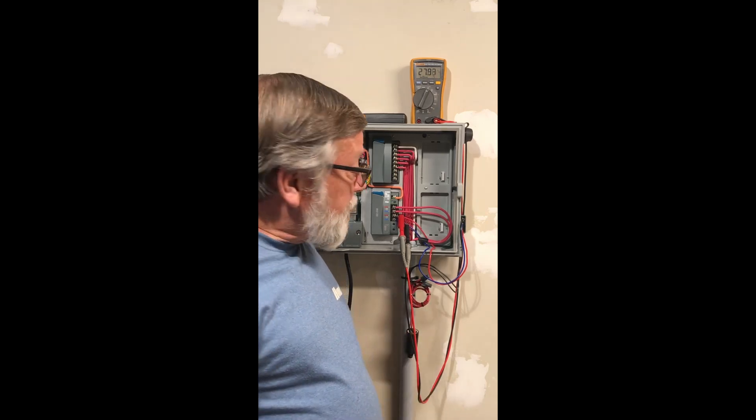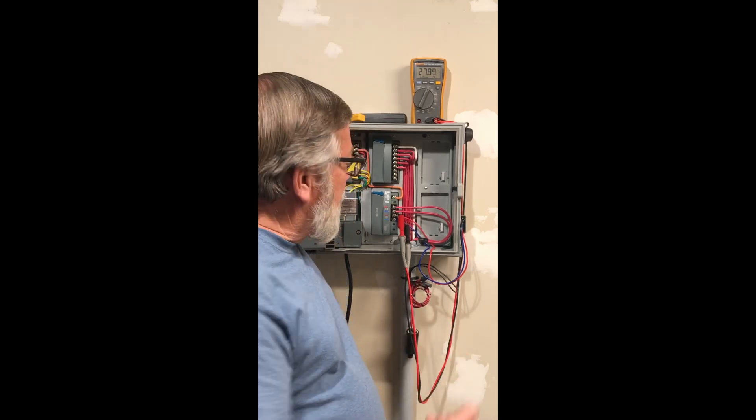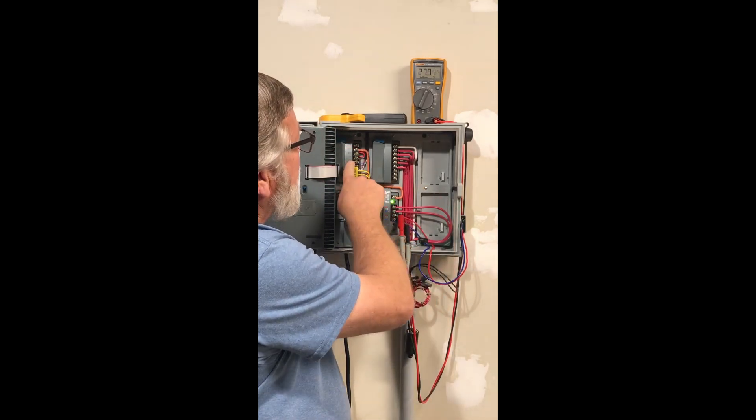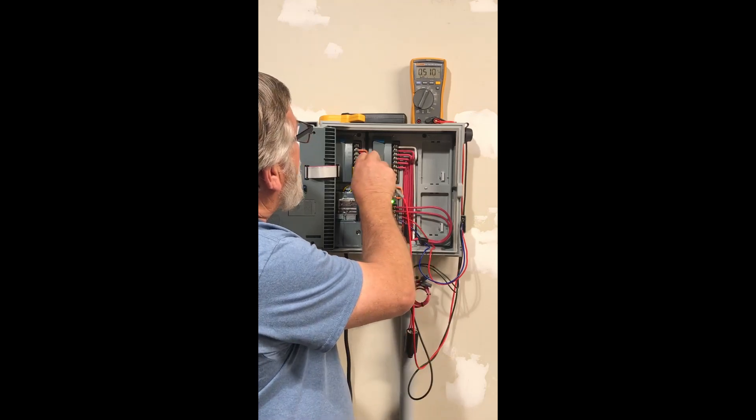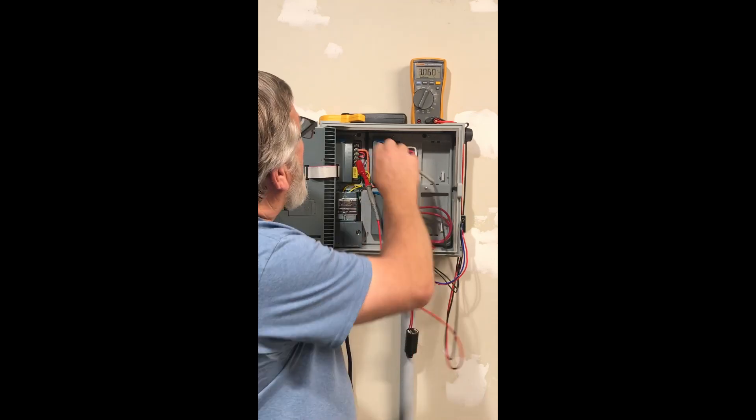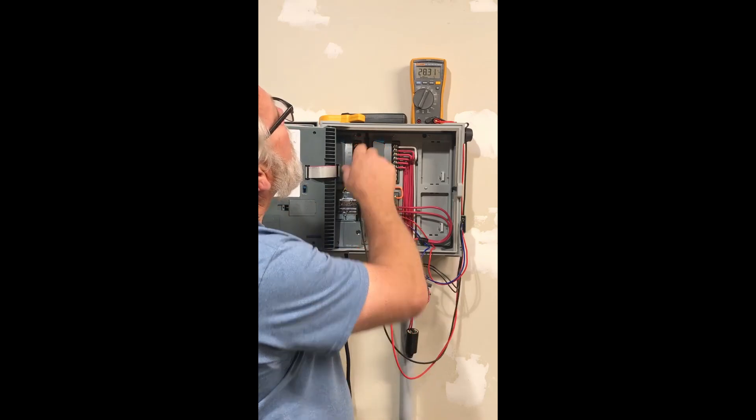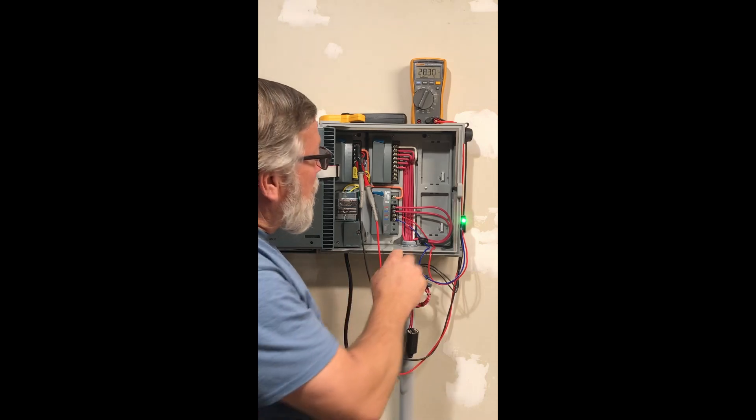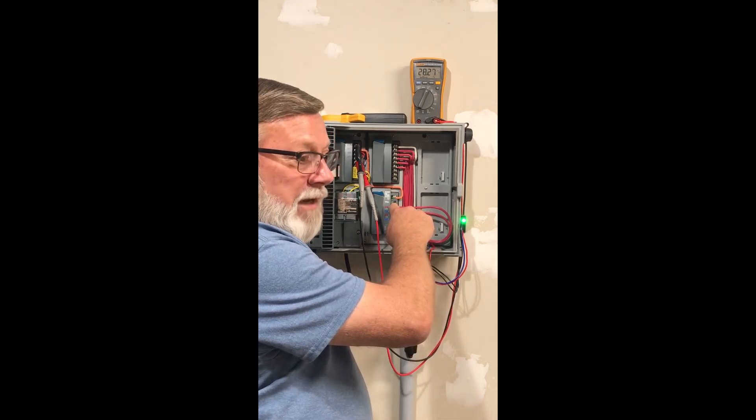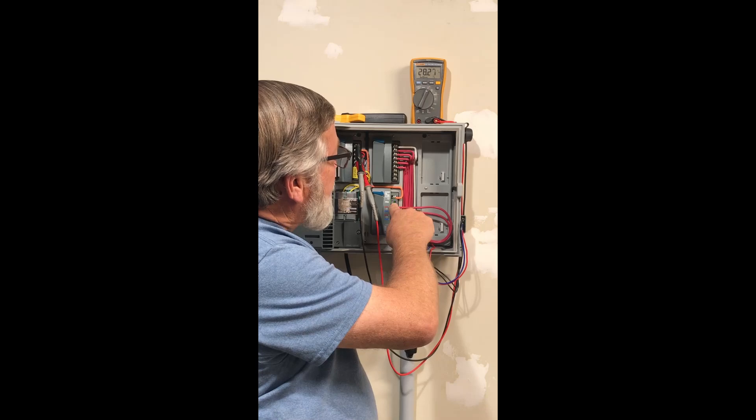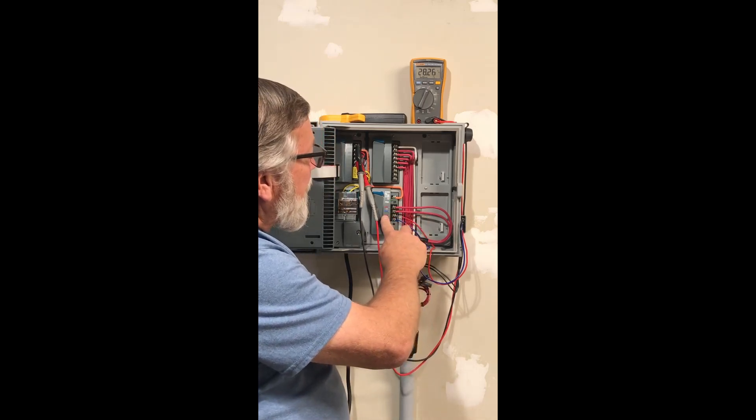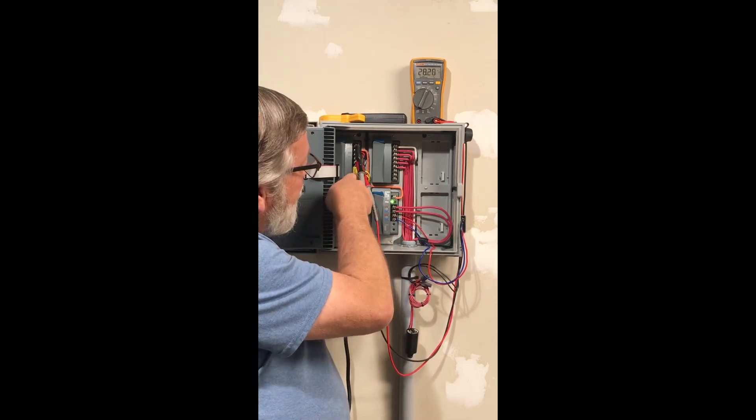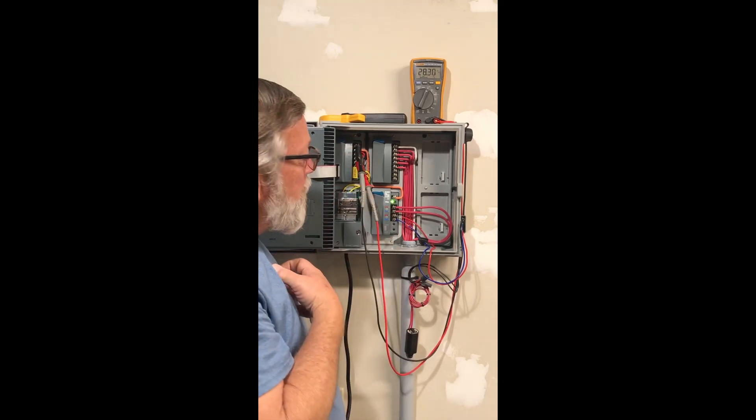So we've given you some diagnostics. So it's very simple. If you have no light here you need to come up here and check for voltage and so what I usually tell people is to come up here and go between the test terminal and any one of the commons. If I have voltage like that then I know that I have voltage to here and if this thing is still black and blank and not even lit up then I know there's probably something going on with this module. If I have no voltage here then I know there's something going on here and I keep diagnosing down through the transformer. I just find out if the transformer is giving me 24 volts.